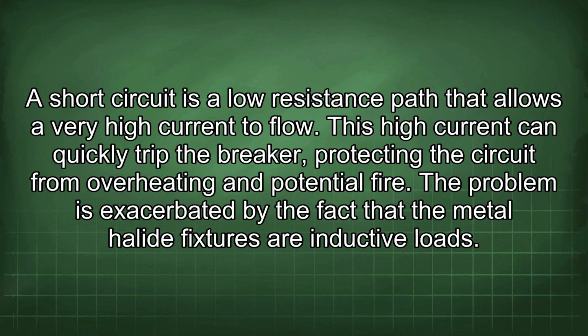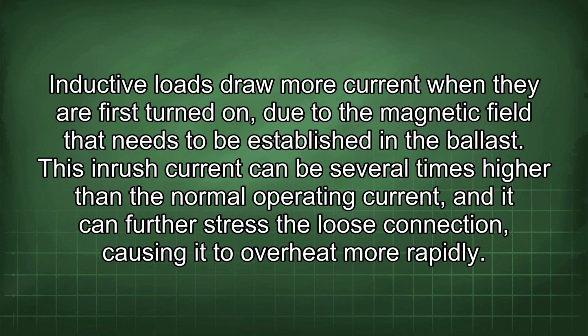The problem is exacerbated by the fact that the metal halide fixtures are inductive loads. Inductive loads draw more current when they are first turned on, due to the magnetic field that needs to be established in the ballast. This inrush current can be several times higher than the normal operating current, and it can further stress the loose connection, causing it to overheat more rapidly.